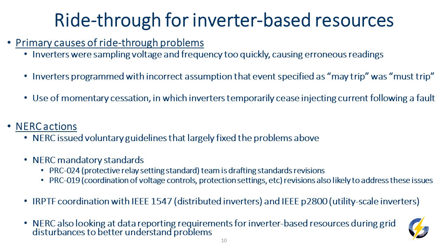So the solution here was pretty easy - just to slow down the sampling rate of the device so that it wasn't getting an erroneous initial reading, but instead getting a much more settled reading of voltage and frequency after a certain period of time, and then deciding what to do. After the guideline, I think that's largely been fixed.